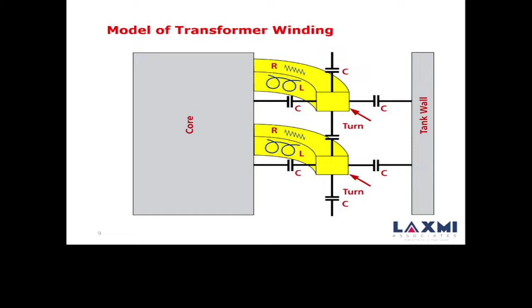Resistive component means you are directly related to your conductor. Inductive means mutual inductance and self-inductance. Capacitive means all the insulations in your transformer, like interwinding insulation, interturn insulation, or tank to winding CH insulation, or winding to core CL insulation. All those insulations come into the picture. So if you measure all this RLC, indirectly any problem in your transformer, either mechanical, electrical or dielectric, you are going to capture by SFRA. That is the beauty of SFRA.